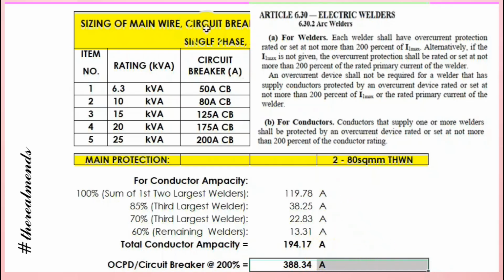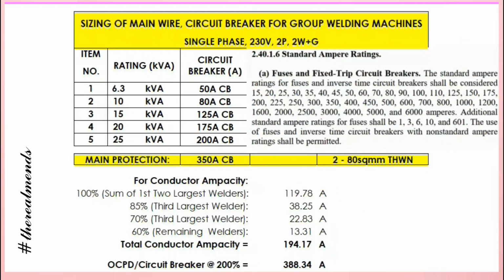Refer to PEC 2.40.1.6, standard ampere ratings. The value we got is 388.34 amperes, so it should be not more than 200%; we cannot go beyond that. It falls between 350 and 400. If we use 400, it will exceed the 200%. So the 350 is the one we use, since it does not exceed 200%. Therefore, our circuit breaker will be a 350 ampere circuit breaker. The PEC is fairly clear on how to size the wire and circuit breaker of our welding machines.